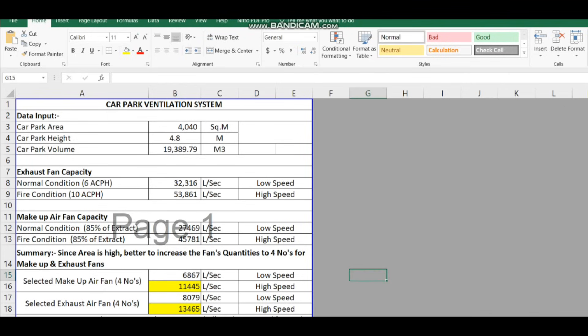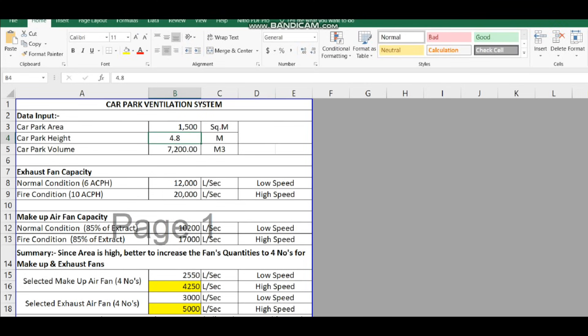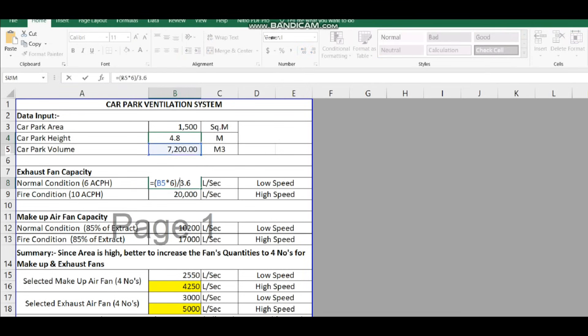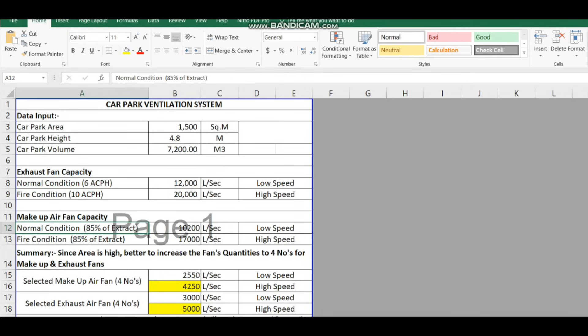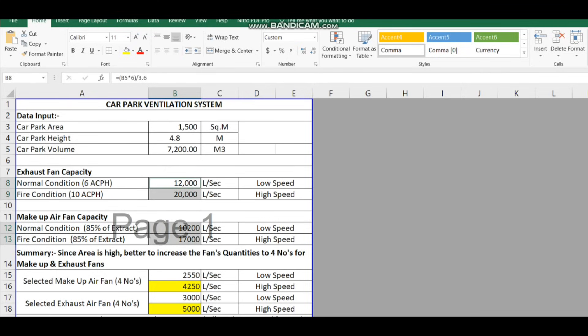As explained, exhaust grills are kept over the cars and fresh air grills are placed in between along the driveway for proper air circulation. In the Excel calculation file, for example: with an area of 1,500 m² and a car park height of 4.8 m, total volume is 7,200 m³. At 6 ACH (normal mode) the exhaust fan flow is 12,000 L/s, and at 10 ACH (fire mode) it is 20,000 L/s. The makeup air fan is 85% of exhaust.